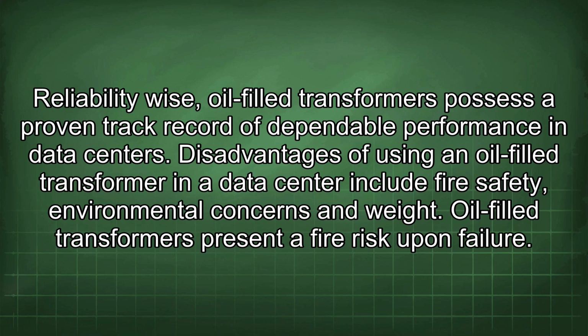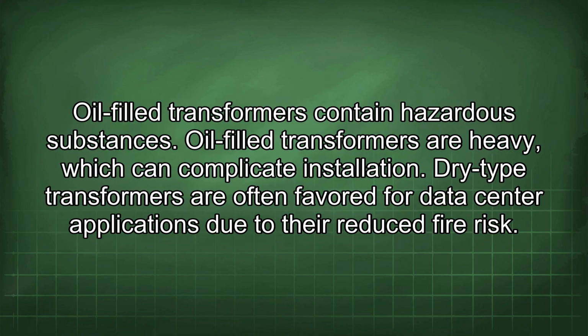Disadvantages of using an oil-filled transformer in a data center include fire safety, environmental concerns, and weight. Oil-filled transformers present a fire risk upon failure. Oil-filled transformers contain hazardous substances. Oil-filled transformers are heavy, which can complicate installation.